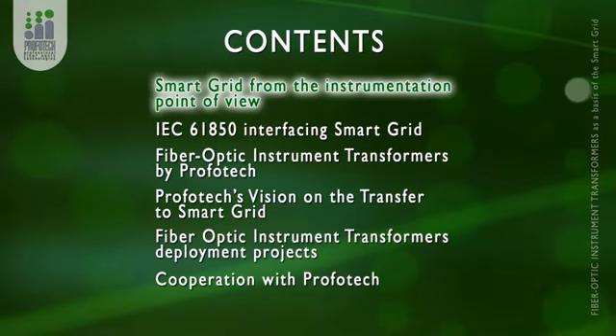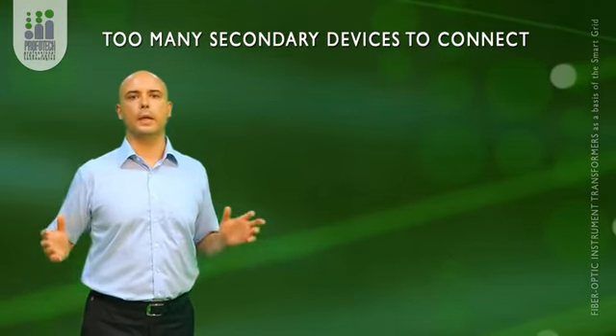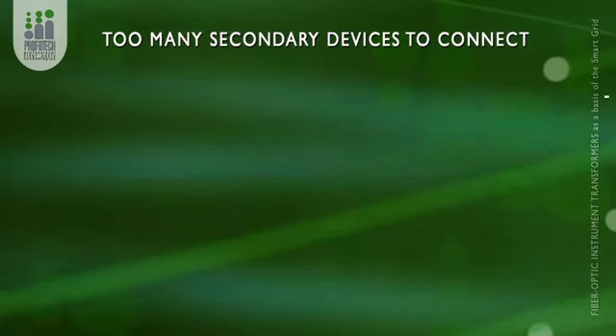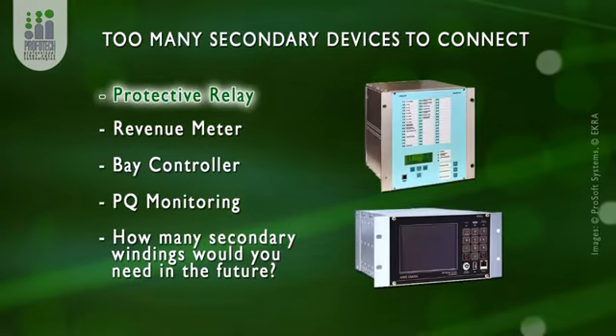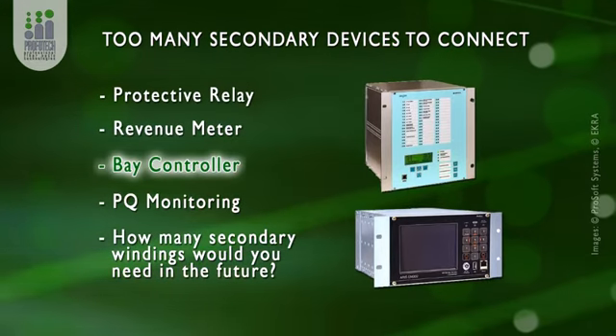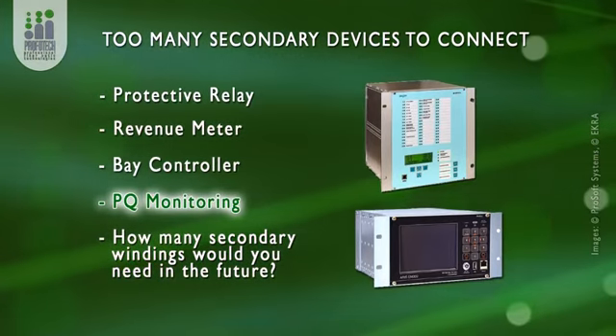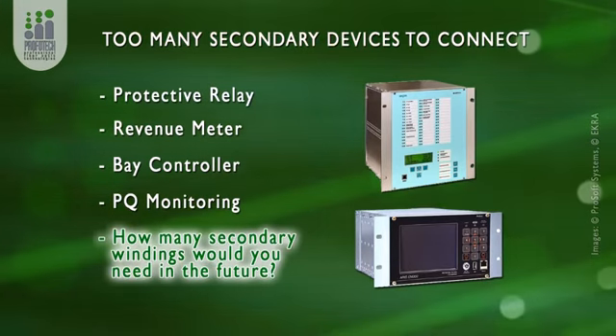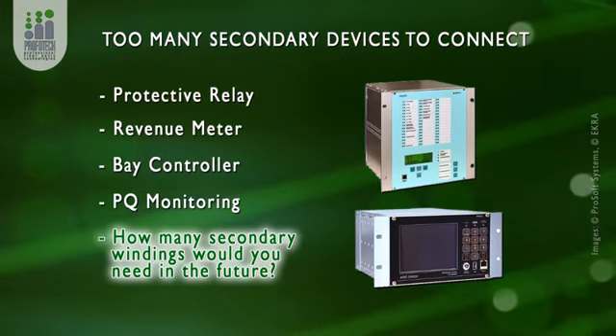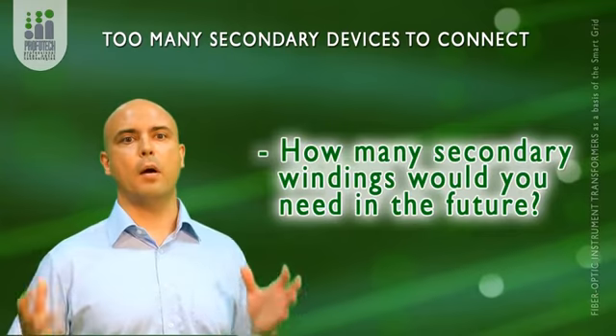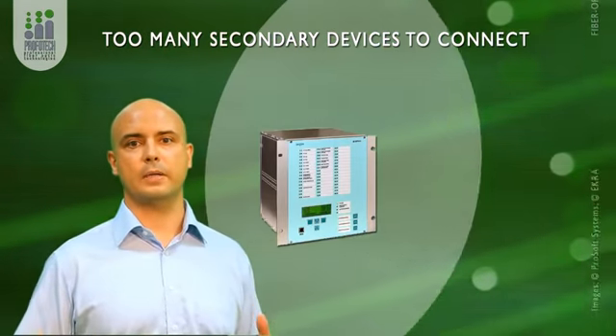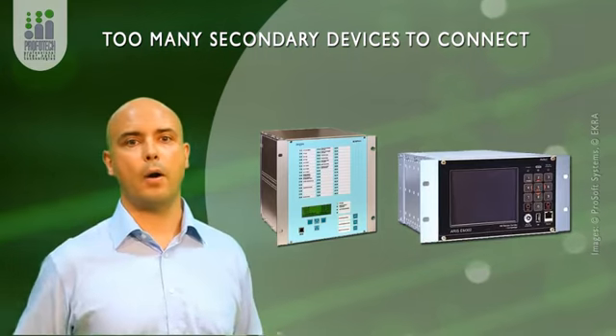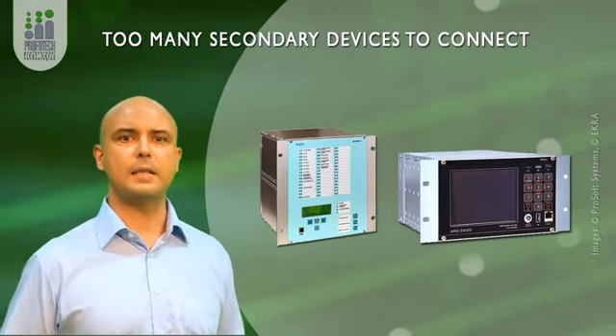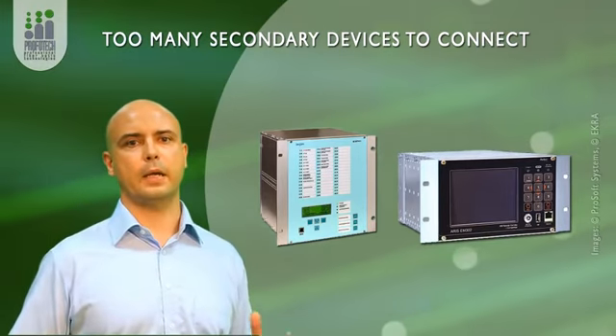Challenge number 1. There are too many secondary devices that we need to connect to the instrument transformer. First, there are protective relays that are followed by revenue metering, bay controllers, and power quality monitoring. We are aware that smart grid deployments will probably need some additional equipment connected, but we currently have a limited number of secondary windings of the instrument transformer as well as limited power on the winding. And this is the challenge for the conventional electromagnetic instrument transformer.